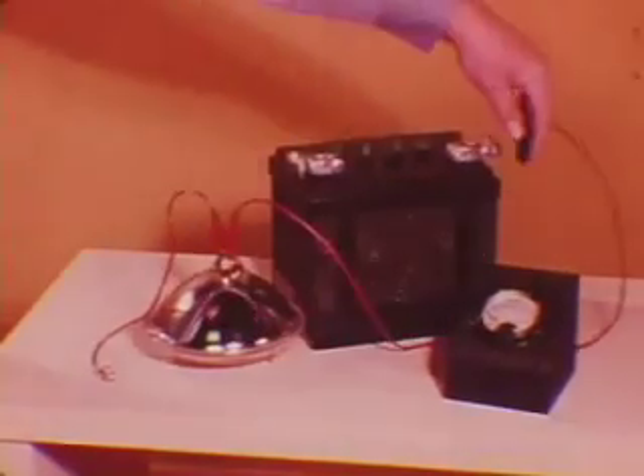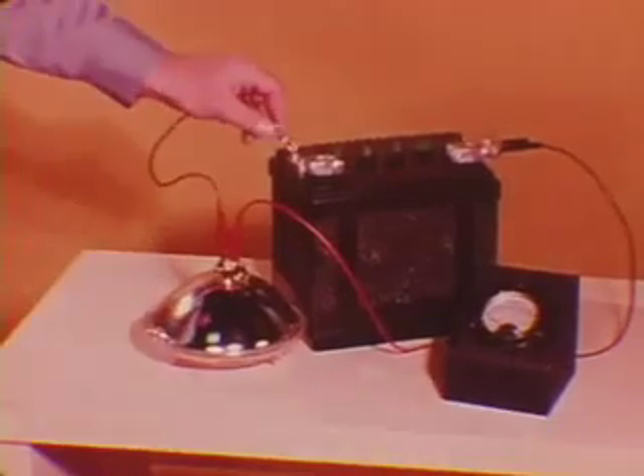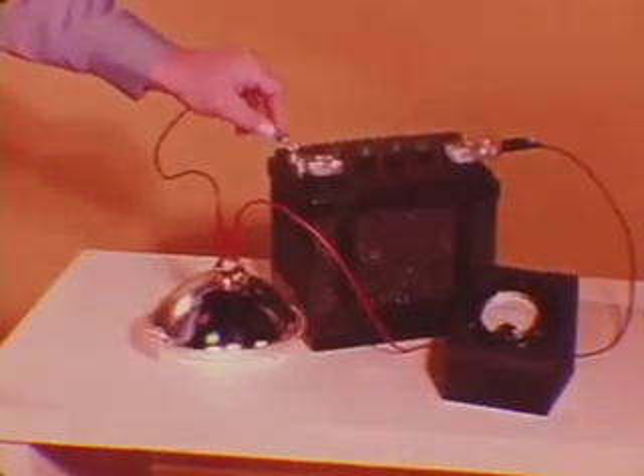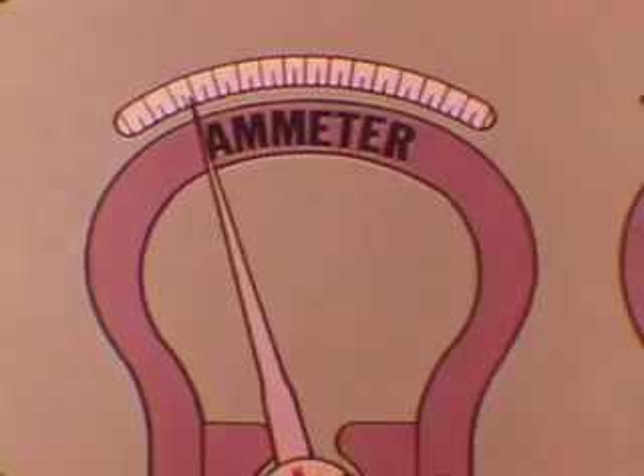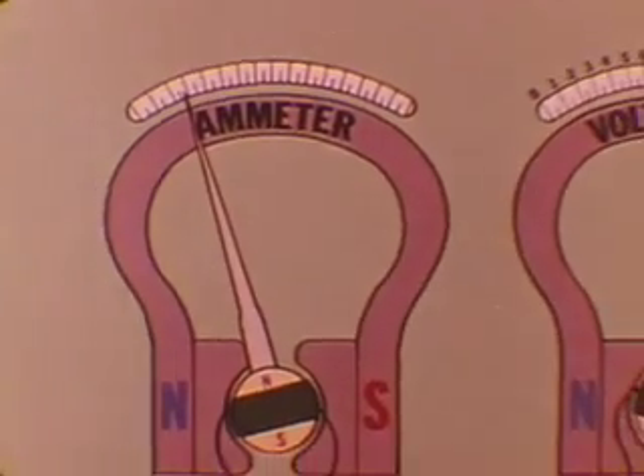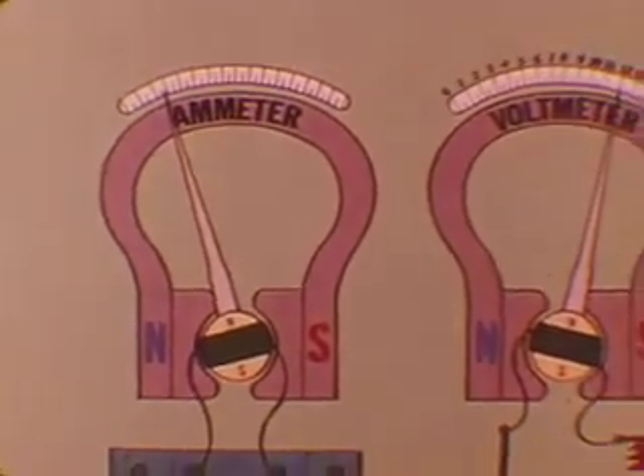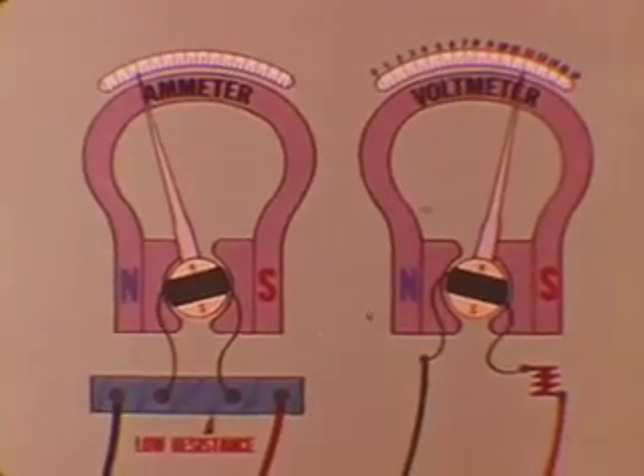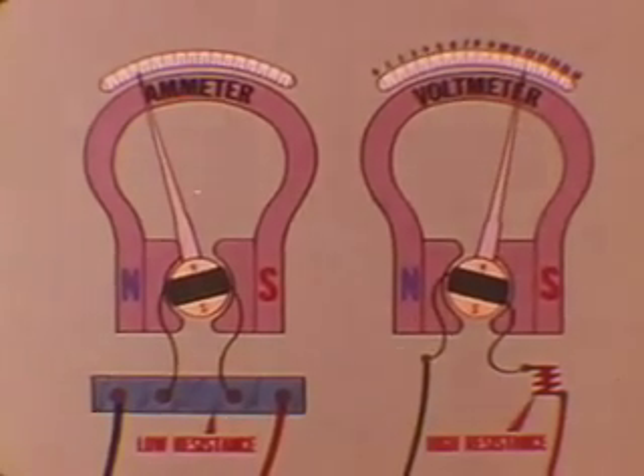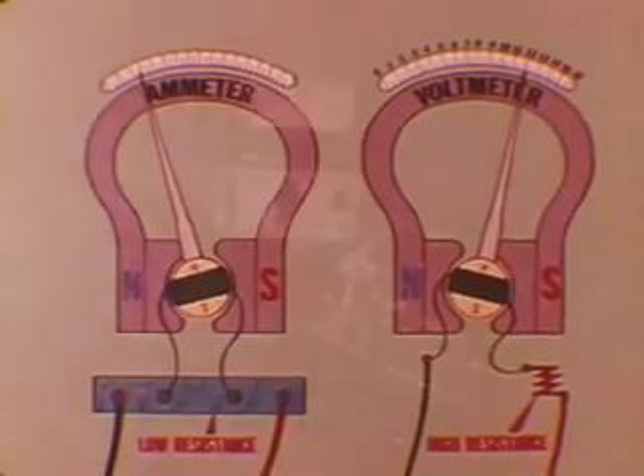Before connecting an ammeter, make sure there's enough resistance in the circuit you're testing to limit the amount of current flowing through the circuit and the meter. Unlike the voltmeter, an ammeter doesn't have enough internal resistance to protect itself against excessive current flow and serious damage. Be sure and use an ammeter with a high enough capacity to handle the flow in the circuit you're testing.